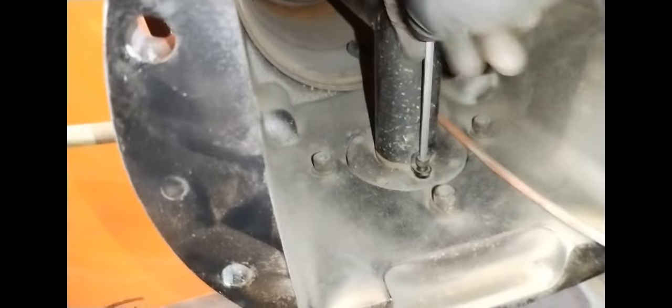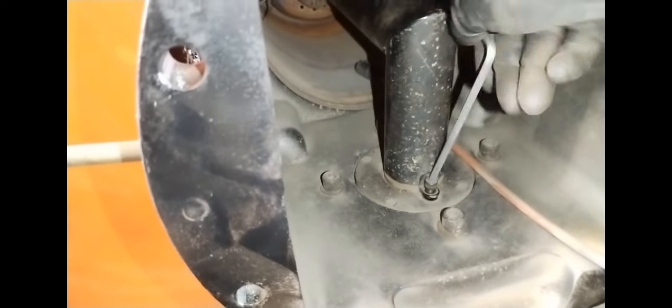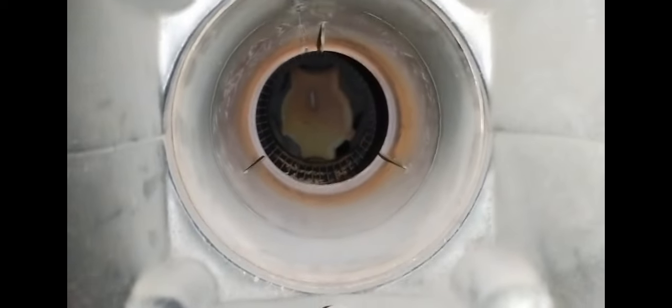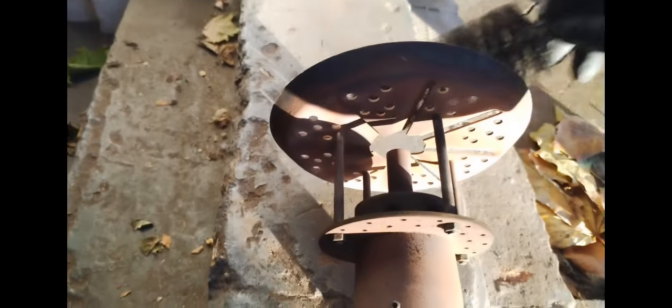Let's move in the Allen key. A lot of the time these lockouts, as I'm sure you know, are because the probes need cleaning, because a lot of these units pull in a lot of dirt and dust from plant rooms, and these are lighting up all the time, so they just need to be cleaned. Here's a look inside the unit. It looks like there was a bit of debris inside there. And just giving it a brush through.